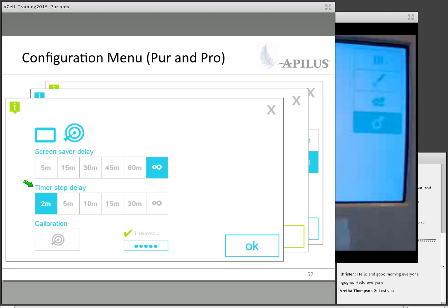The timer stop delay is essentially when you're in the treatment modes and you're working on a client and you have a timer set. Remember I set a timer for 2 hours. Well, let's say that somebody knocks on the door. So I put everything away and I have to go to the front to see who's at the door. My timer keeps going because I left quickly and forgot to pause it. After 2 minutes of nothing happening, and nothing happening means no pressing on the foot pedal, remember, that's how the machine can really gauge what you're doing, so I haven't pressed on the foot pedal for at least 2 minutes, my timer will pause automatically.